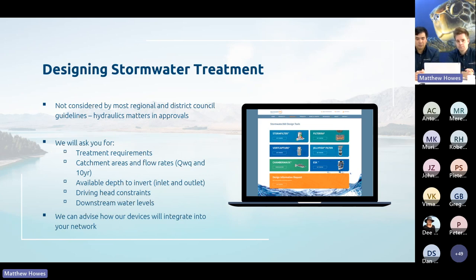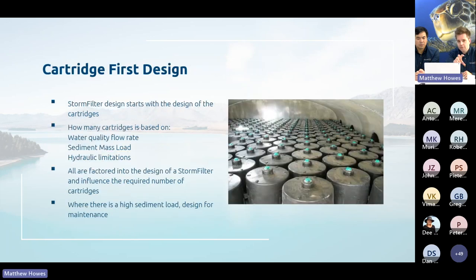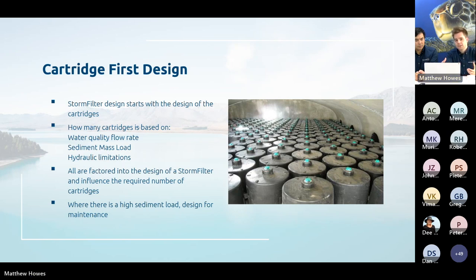We can advise how our devices will integrate into your network, so it's really important to reach out during the design phase — more information is in our hydraulics webinar. With the Storm Filter, we always start with the cartridges first, not the manhole size. We look at the water quality flow rate, whether hydraulic limitations mean we need 46cm rather than 69cm cartridges, and whether there is an increased sediment mass load that means we need more cartridges to avoid onerous maintenance. All of that feeds into how many cartridges are needed.